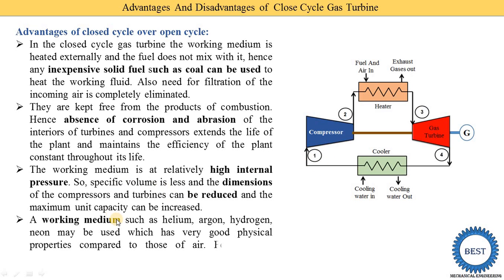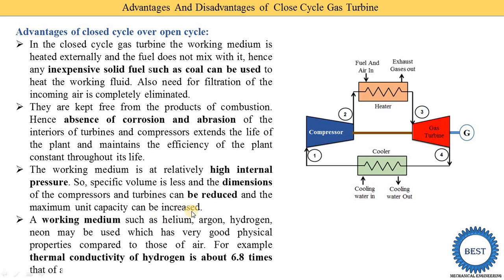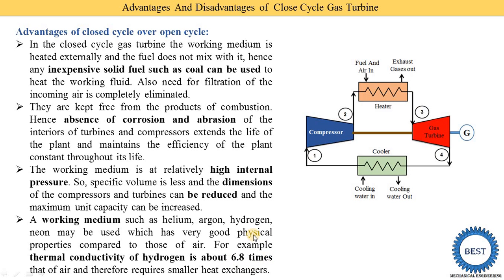The next advantage is that the working medium can be substances such as helium, argon, hydrogen, or neon, which have very good physical properties compared to air. Depending on the size of the plant, we can use working fluids other than air. For example, the thermal conductivity of hydrogen is about 6.8 times that of air, and therefore requires smaller heat exchangers.